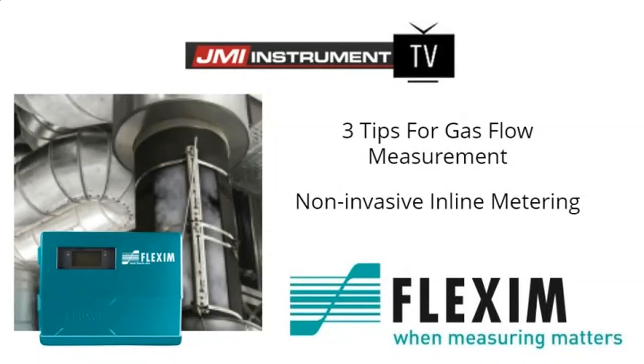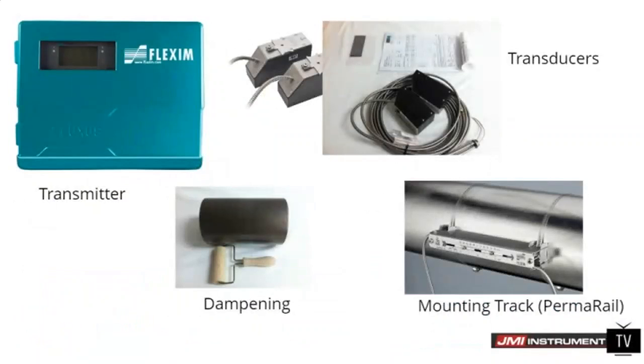So, we'll talk a little bit about Flexim today. If you're not familiar with Flexim, it's an ultrasonic flow meter company based in Berlin. Four shareholders own the company. Today we're going to talk specifically about gas measurement. And with gas measurement, it is the same theory of operation. It's transit time or time of flight. The main thing that's different here is the dampening material, and we'll talk about that a little bit, and the transducers, the type of wave that we use.